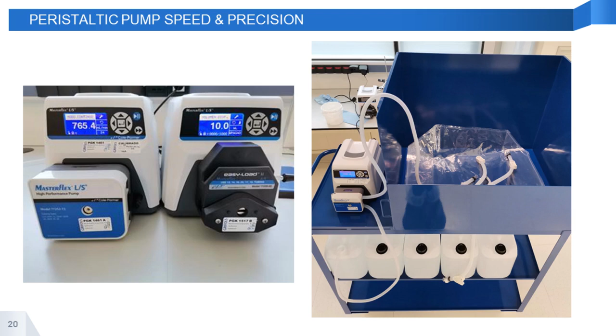As you see, with the performance head and the biggest size tube, the pump goes up to 3.4 liters per minute. We are using it now in my lab to transfer big amounts of liquid. In the slide, an assembly that we have made in my factory is shown. There on the right is a metal structure with 3 floors. On the first 2 floors, bulk reagents are located in their original containers, as we receive them from the supplier. And above them, we have our peristaltic pump on the left and a big intermediate container on its right, which is currently 200 liters in size, but it could easily be scaled up. So liquid can be dispensed directly from that 200 liter intermediate container later on into some final tubes or bottles.